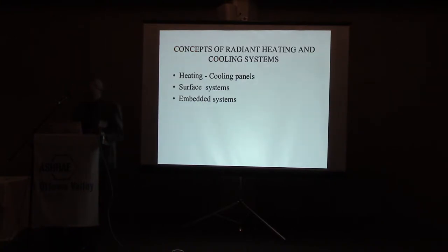When we today talk about radiant systems, normally what we have tried to define in the standard is systems where more than half of the heat exchange is by radiation. You don't see any radiant system which has 100% energy exchange by radiation. There's always some convection. But more than half should be by radiation, then we will call it a radiant system. You can either have panels, we can have what we call surface systems or embedded systems. So let me try to show you how we distinguish between those.